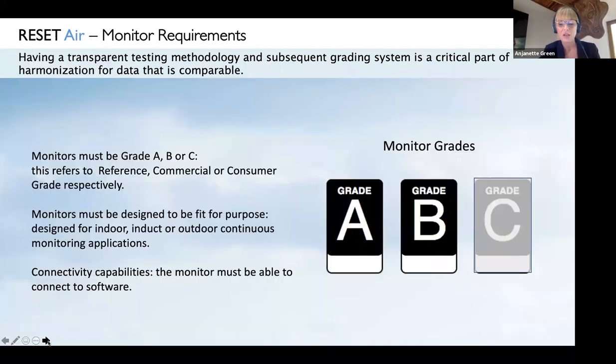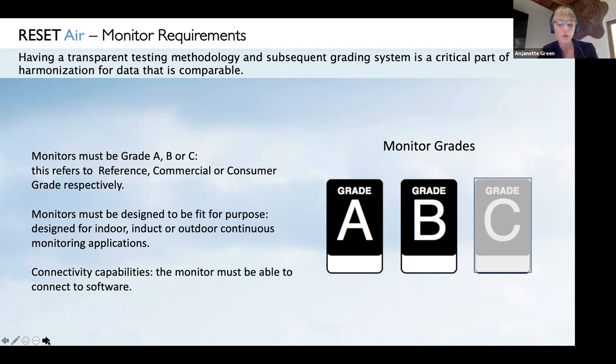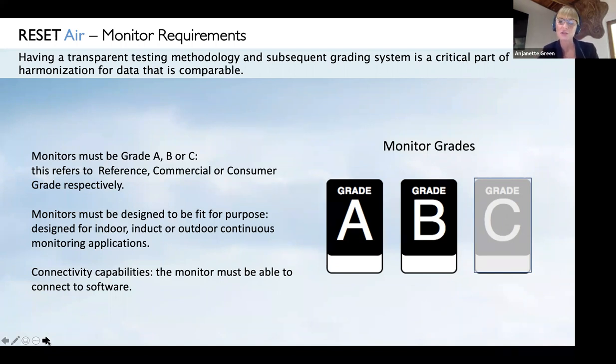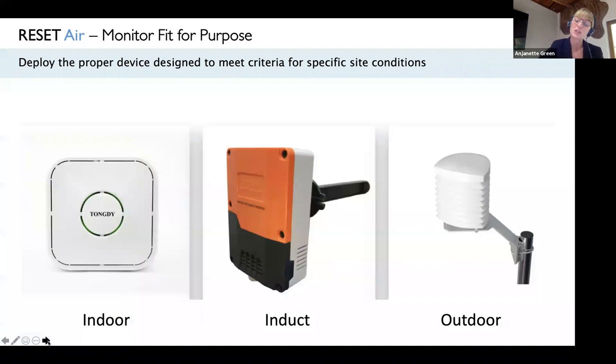Reset has a transparent testing methodology for monitors — a critical part of the standard. Reset classifies monitors using a graded system: A, B, and C. A Grade A monitor is like a federal reference device. Grade B is a third-party accredited device. Grade C is consumer grade. There's a place in the market for all of these, but only Grades A and B are allowed on Reset projects. Examples include an indoor monitor, an in-duct monitor, and an outdoor device.